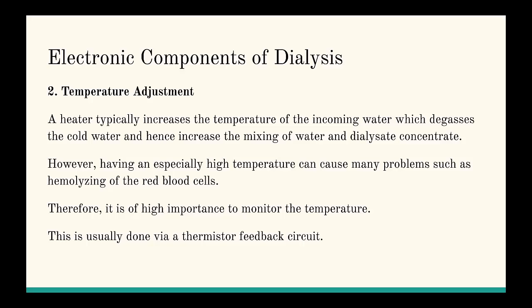But heating can cause problems if the temperature goes too high, causing red blood cells to hemolyze, which, as you'll remember from biology, is the bursting of red blood cells. So it's very important to monitor temperature, and that's why dialysis devices generally use a thermistor feedback circuit to control it.